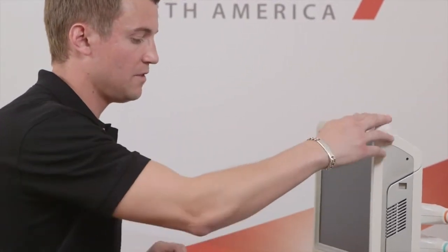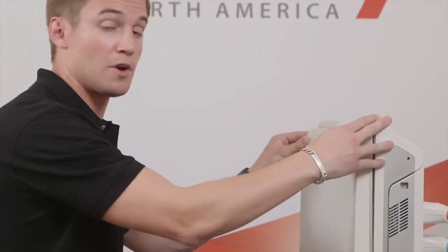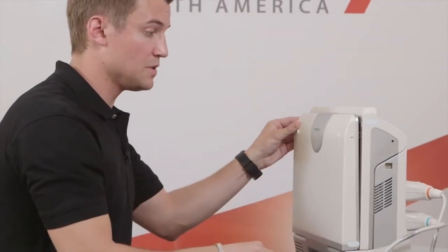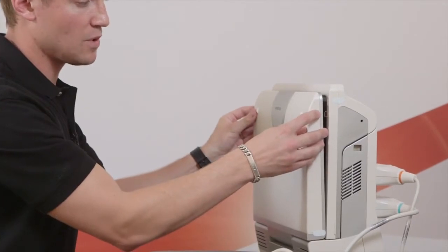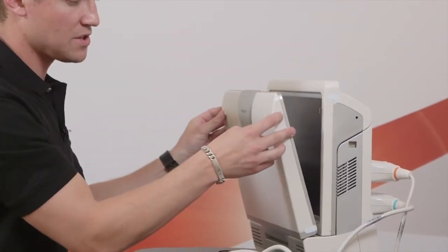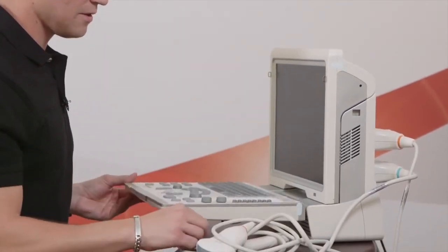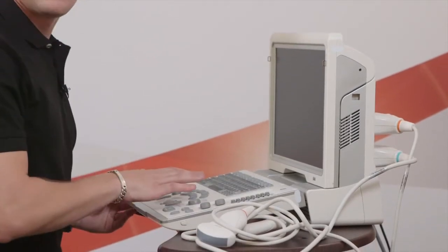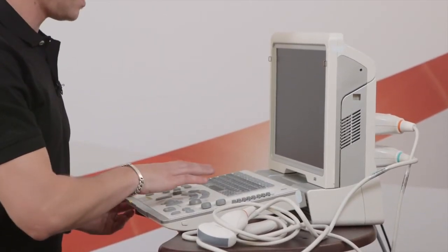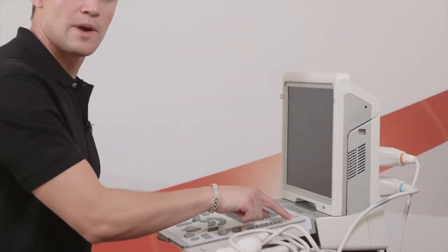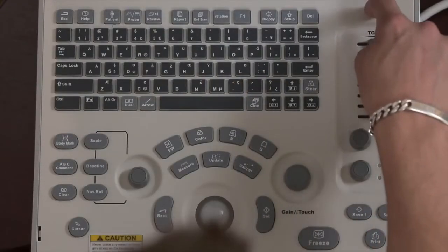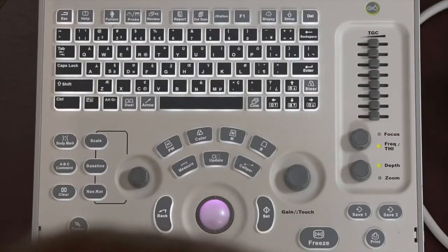As you put the Z6 on a table or a cart, wherever you're storing the machine in order to use it, you'll notice that there's two little tabs, one on each side of the machine, and when you pinch those, it'll bring the lid down and you'll see the full layout of the console and display here. Note up in the right corner is the power button, so we'll go ahead and press that power button. It'll take about 25 to 30 seconds to boot up.